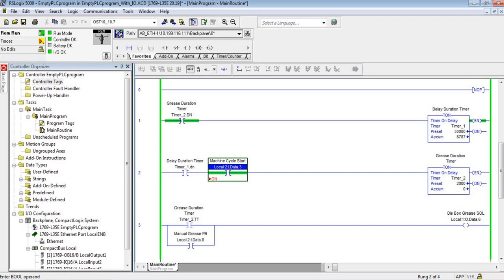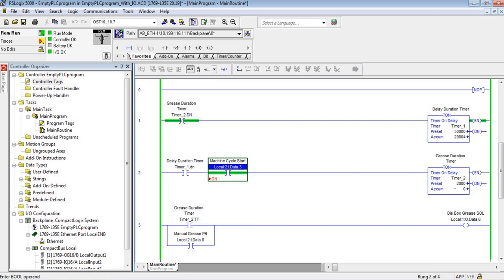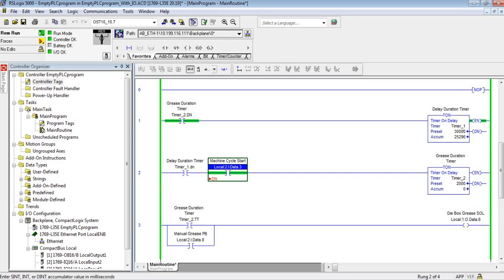It's a motor starter or logic relay that's in the panel. You could probably get away with using an internal to the PLC, but there are some uses for relays in the actual panel. If the machine's running and it's been 30 seconds since we greased, grease for two seconds. In real life I do two hours, but in this case 30 seconds. When this timer is done, it'll reset itself. This done bit turns on and blocks this path, so timer one will die and lose power. That will kill the done bit for it, which will kill timer two. When timer two dies, timer one starts timing again because the done bit turns off on timer two. This is kind of normal stuff - an auto-resetting timer system.